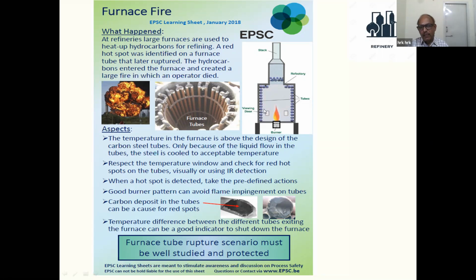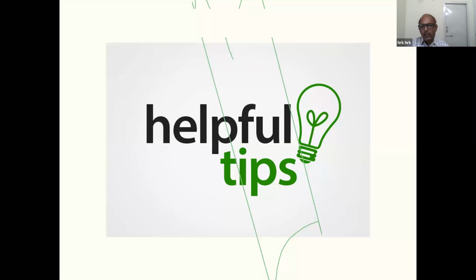So we have these openings for viewing temperature, the viewing doors. If we are able to take thermography through the viewing doors, we can know the condition of the pipes, whether they are in a hot condition beyond the permissible range. So we can prevent the accidents.